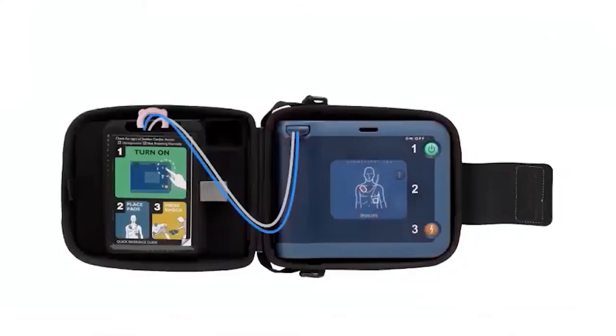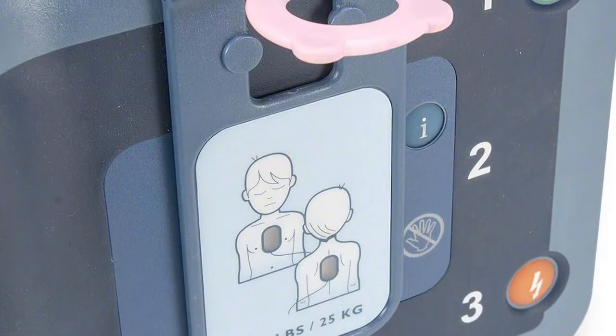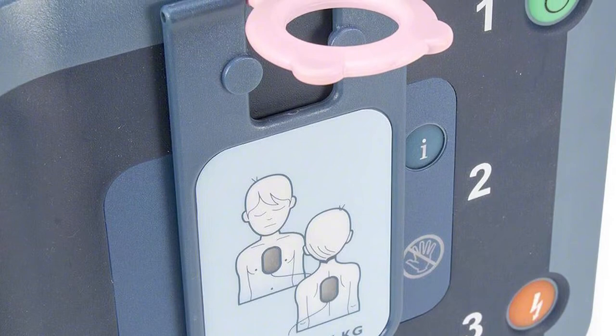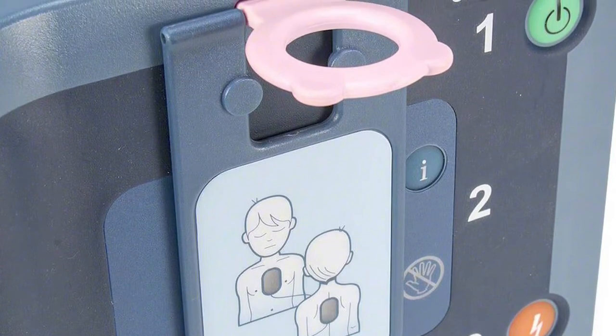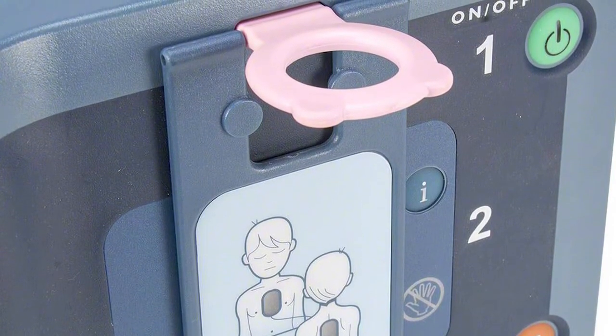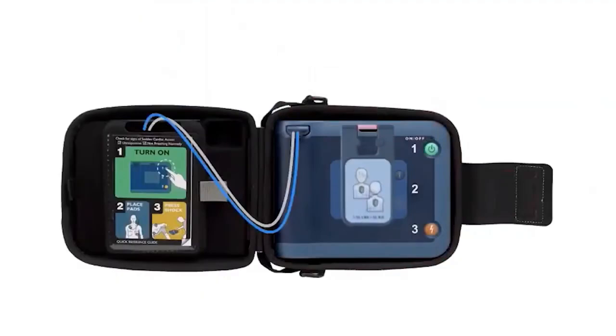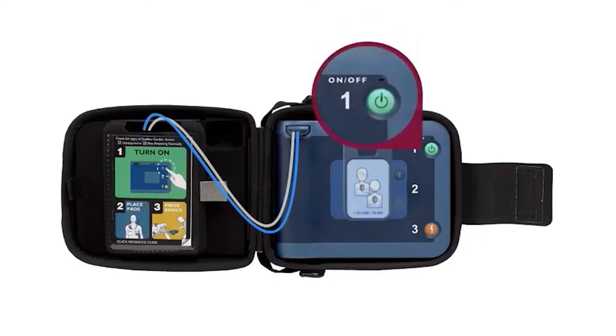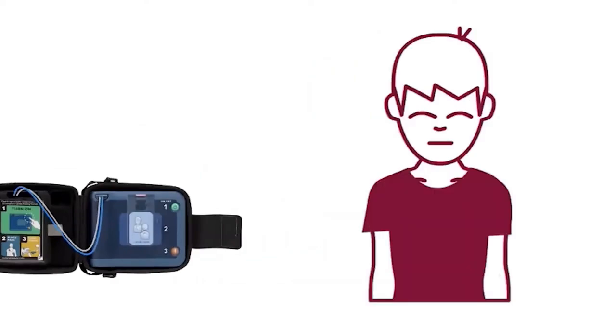To use the infant-child key, insert the key into the slot at the top center of the front panel. The pink portion of the key will pivot into the slot, while the front of the key lays flat across the front of the unit and displays the infant-child pad's placement diagram. When the key is inserted, the unit will announce infant-child mode and will automatically reduce the defibrillation energy from the adult dose of 150 joules to 50 joules. The CPR coaching will change to infant-child coaching.